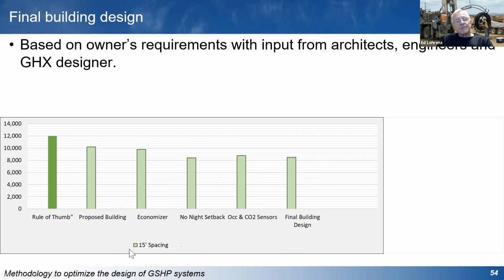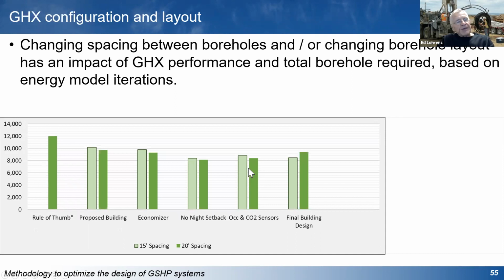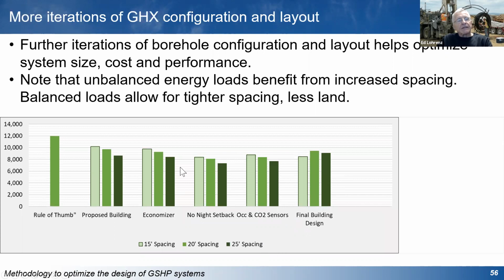These were all based on 15-foot spacing initially. So what happens if we increase the spacing between the boreholes, bumping it up from 15 to 20 feet? In the buildings that were still a bit unbalanced, increasing the spacing reduced the total amount of drilling that was needed, invariably on each one of them. For the final building design, it actually increased the length of the borehole a little bit. Increasing spacing to 25 feet, again you see a further reduction in the building energy models that are unbalanced. So in a project where you don't have an opportunity to balance the loads, or you simply can't get there, increasing the spacing can have a fairly big impact on how much total drilling is needed.